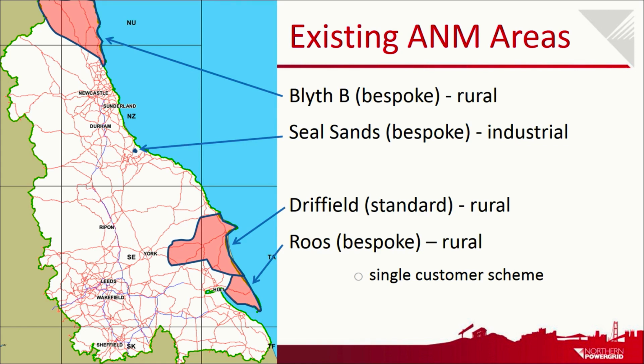And then Roos covers a wide area, but is only actually triggered by a single customer, where we have a single customer in a 33 kV circuit with quite a significant amount of generation beyond them, and they are utilising whatever's left in the circuit when the other generators aren't using it. So that really sterilises that area for new entrants, unless we moved to a wider ANM scheme like we're planning to put in at Driffield. So that's what we've got at the moment.